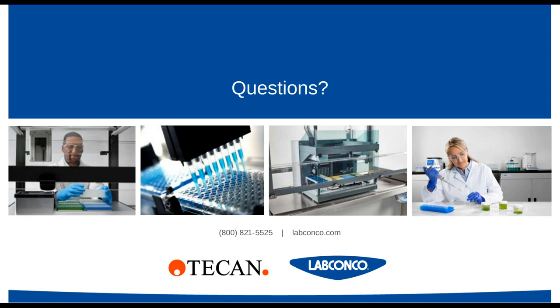Okay, and we have another question that just came in. Does AHU have any effect on BSC efficiency? Not exactly sure what AHU means. It may be air handling unit, which would typically be a generic term to cover the instrument moving airflow in and out of a facility, like a HVAC system. It would typically not have any impact on a biosafety cabinet's efficiency unless the person asking is asking about an air handling exhaust blower that would be supplying exhaust air from a biosafety cabinet. So in that case, if it was an exhaust blower, then it depends on the type of BSC installation.